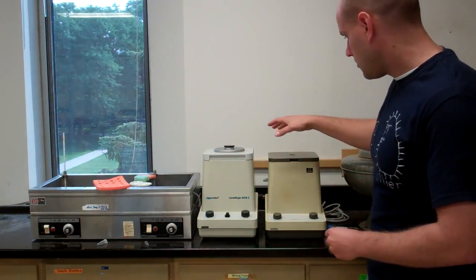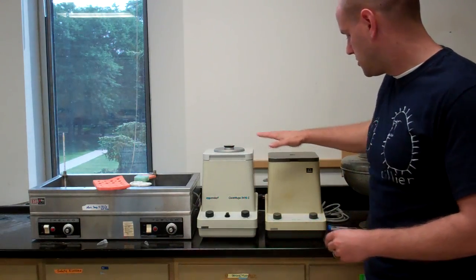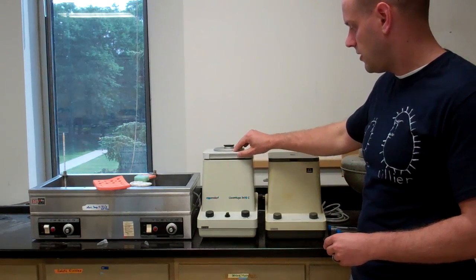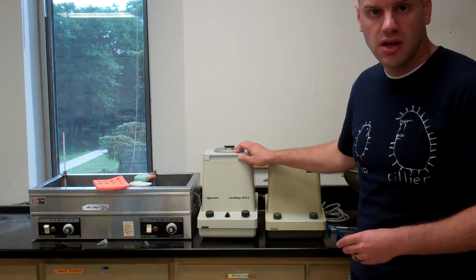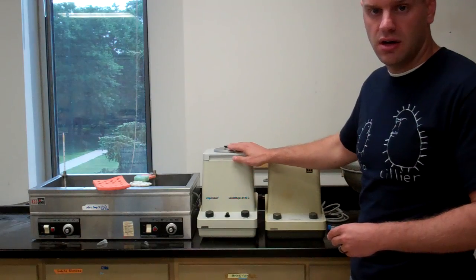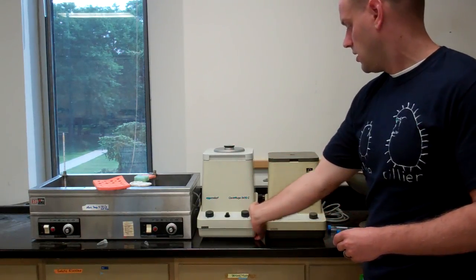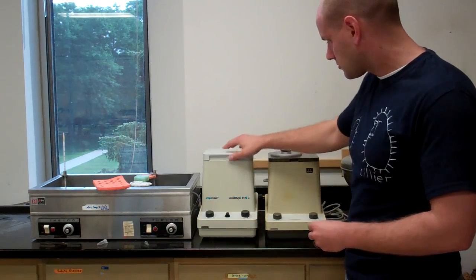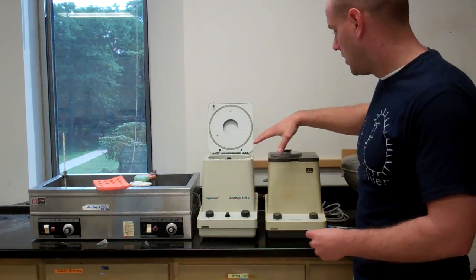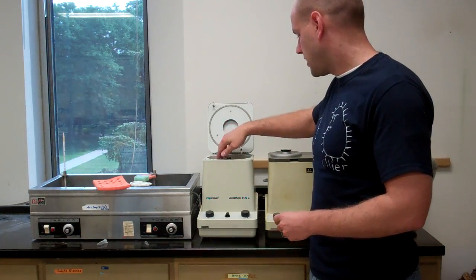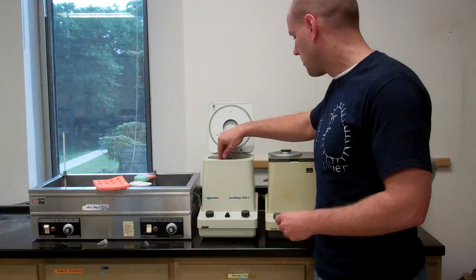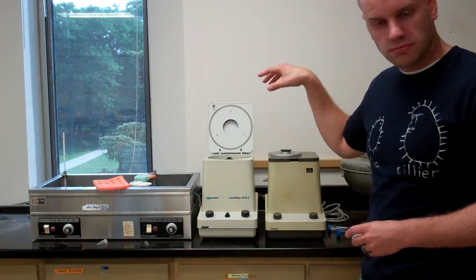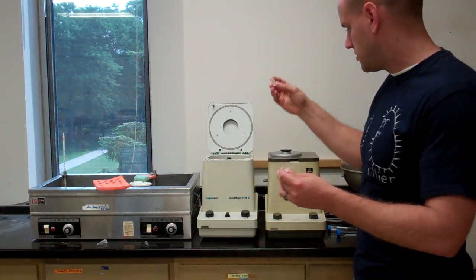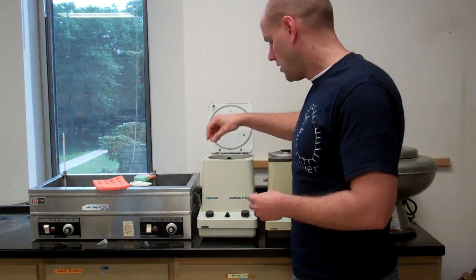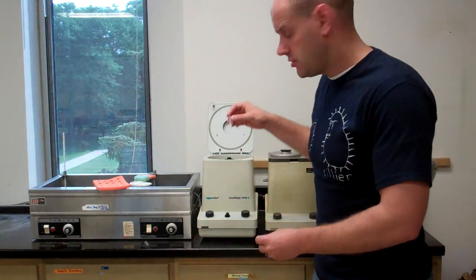You'll notice that both of these are off right now, and when they're off or unplugged, the top is actually locked shut. When you turn these on, the top will then open, and you'll see the rotor inside that has 18 holders in it, and your Eppendorf tubes fit right into those. Your large Eppendorf tubes do.